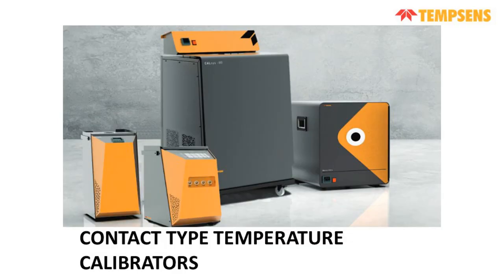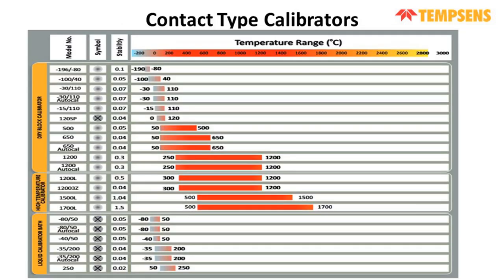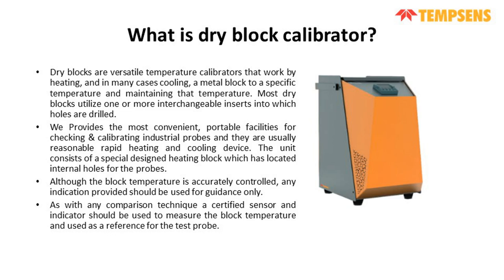So moving ahead with the temperature calibrators. First, I'll be introducing the contact type temperature calibrators. The temperature range for the contact type calibrators is from minus 190 degrees to 1700 degrees centigrade. So what are dry block calibrators? The contact type calibrators are also called dry block calibrators.